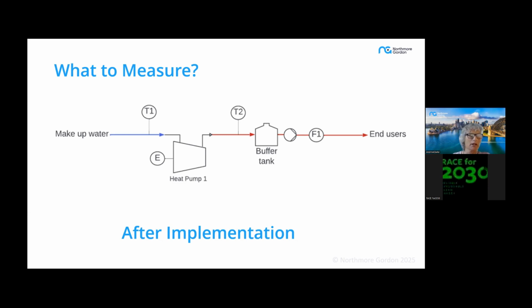consumption change. So similar to the baseline, you want to be measuring your temperature in and out, which essentially, if you're going to be replacing a boiler with a heat pump, you're probably going to be using some of the same piping, and so those thermocouples may just be sitting in the existing pipe. You may have a bigger buffer tank, a new buffer tank, and you want to be measuring the flow from that buffer tank to the end users.